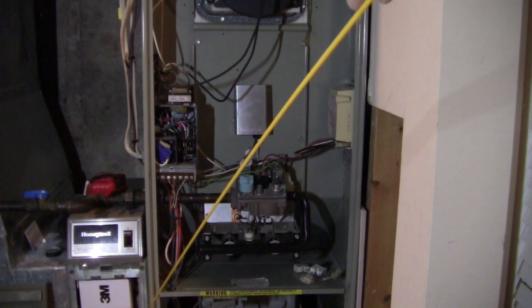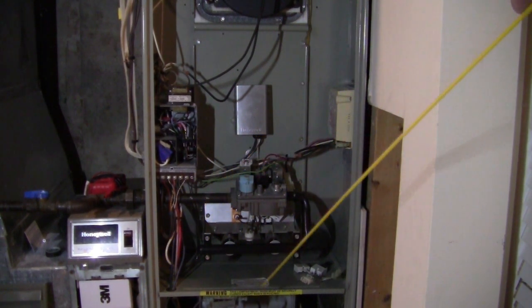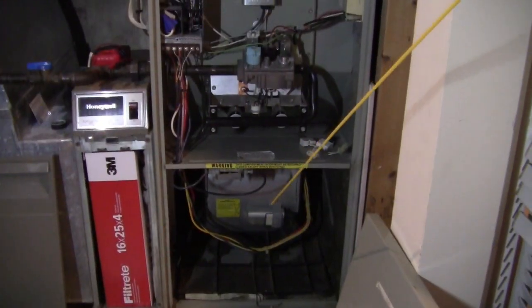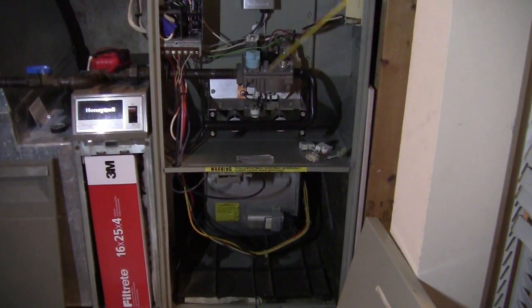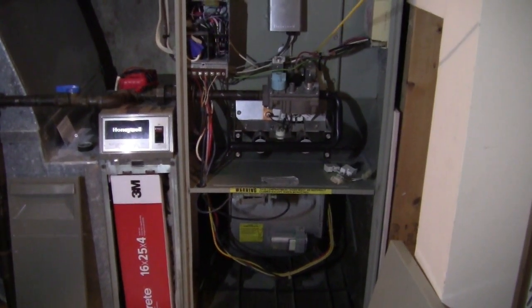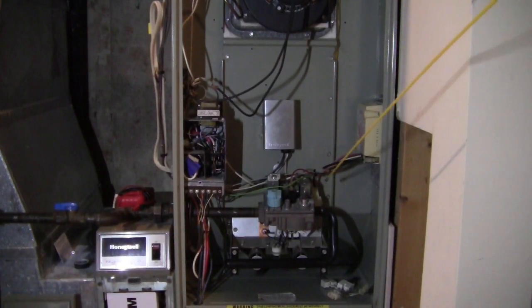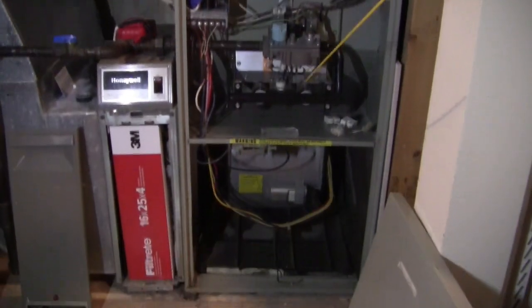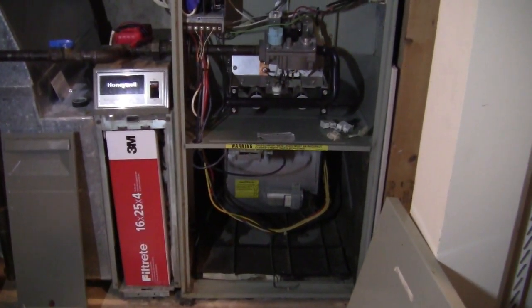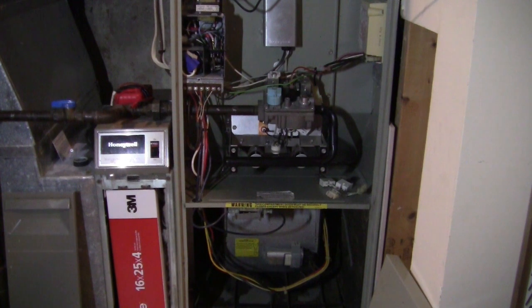If this filter is clogged, or if this fan is not running, or running very inefficiently, very slow, then the air inside this chamber will flow very slow, right? When the air runs slow inside, but the burner keeps providing heat into this chamber, then the temperature over here will be very high. It's going to build up, right?